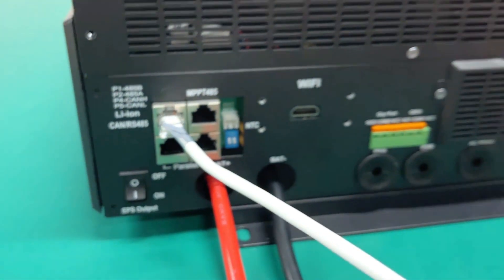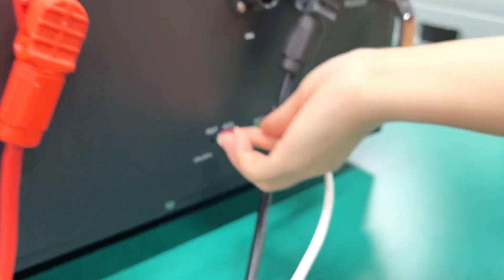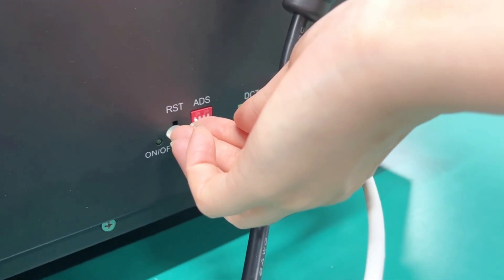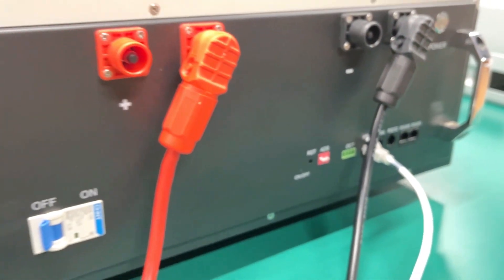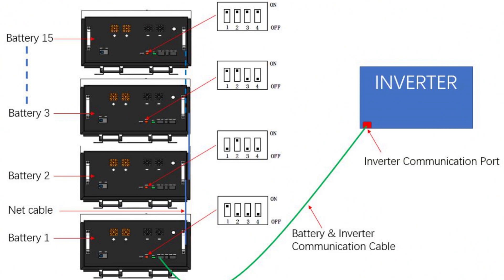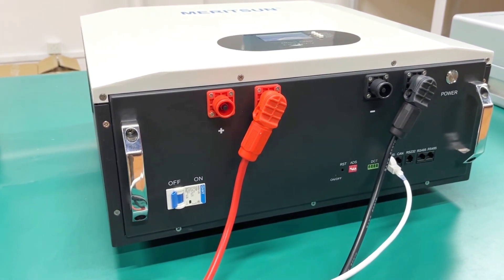Please take this important step: dial the address of the battery to one. When multiple batteries are in parallel to communicate with the inverter, the dial address of the master battery and slave battery must be different. Also, use a LAN or network cable to connect each battery's RS485 port, so the batteries can communicate with each other.